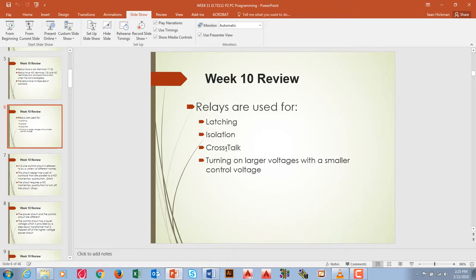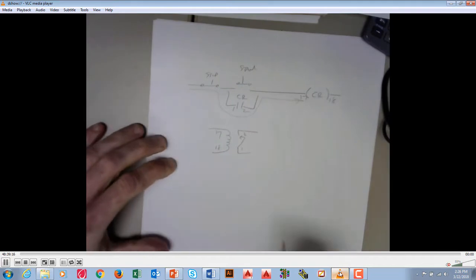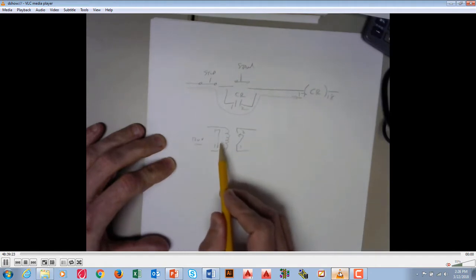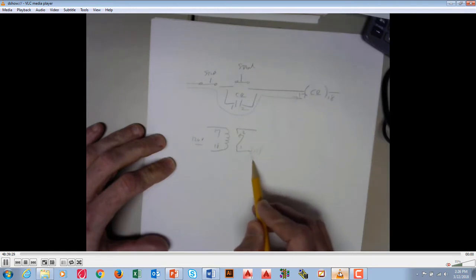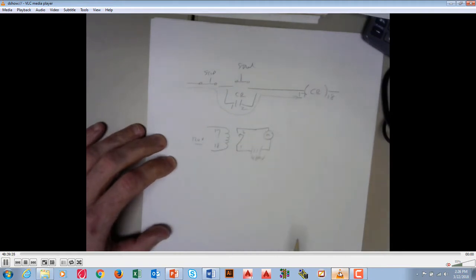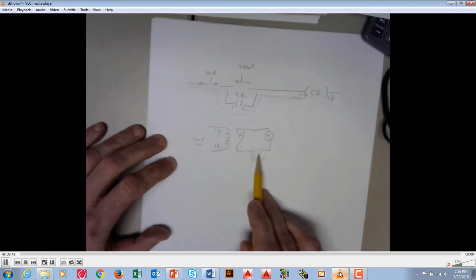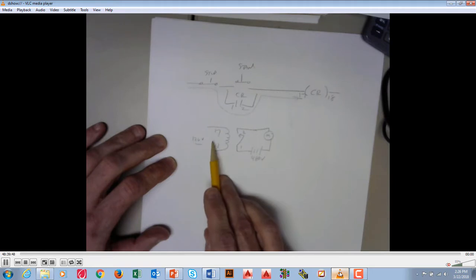The relay is also used for turning on larger voltage with a smaller control voltage. We had 120 volts turning on our relay. But on the other side, because this is just a switch, we could have very high voltage — like 480 volts — turning on a very big motor, a motor as big as this desk. This is a circuit with a load, conductors, a switch, and voltage. So a small voltage control circuit can turn on a very large motor circuit. That's kind of what the lab was about.